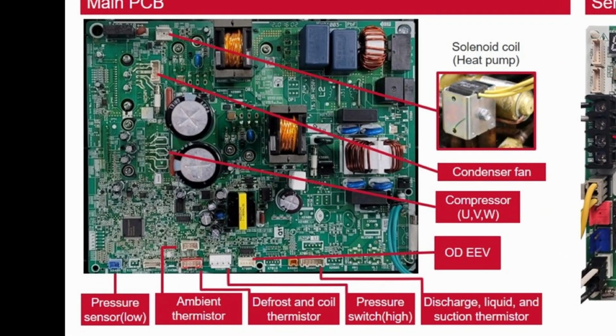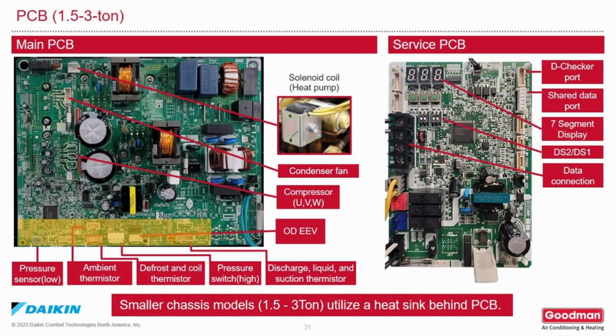On the 1.5 to 3 ton units, the main control board will have a heat sink attached to the back side of it, which are aluminum fins that go out into the airflow to cool the inverter section while the system is running. Across the bottom of the main PC board, you'll see the locations for the pressure sensors, thermistors, and other monitoring devices. You'll also notice the location of the condenser fan connector, which is DC voltage. Also notice the location of the choke coils, which are part of the noise filter. Here are the smoothing capacitors, which are part of the inverter section. There are also the U, V, and W terminal access points for the compressor.